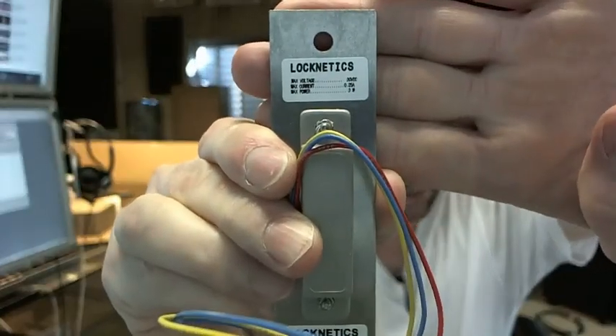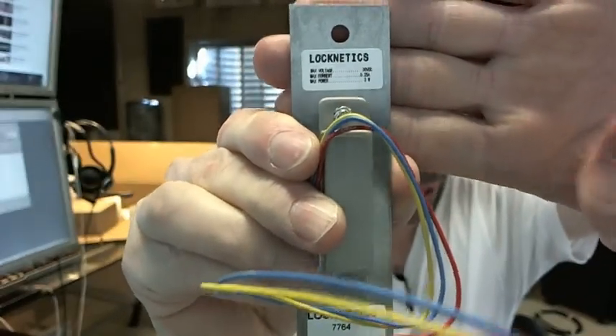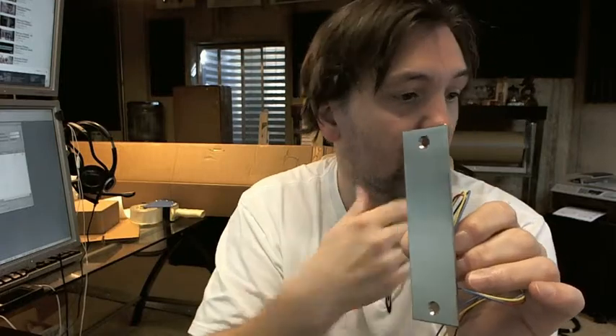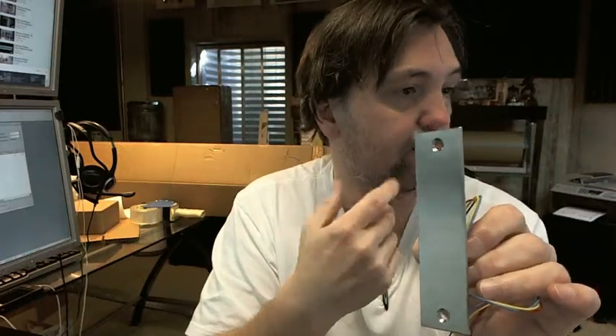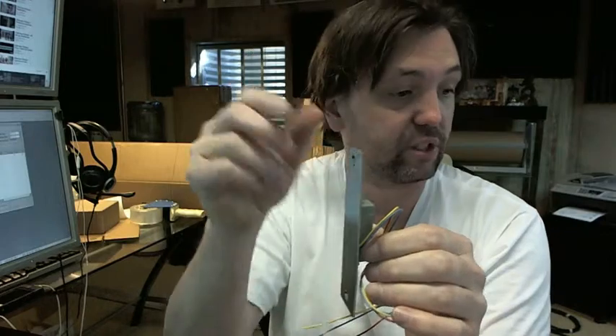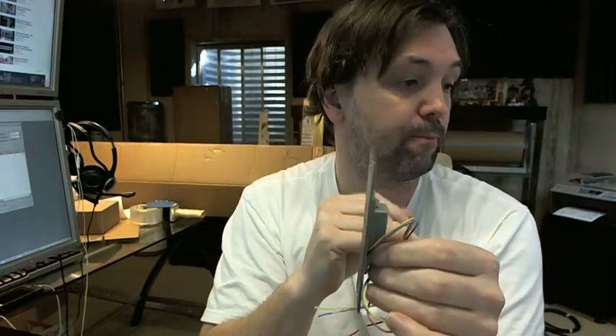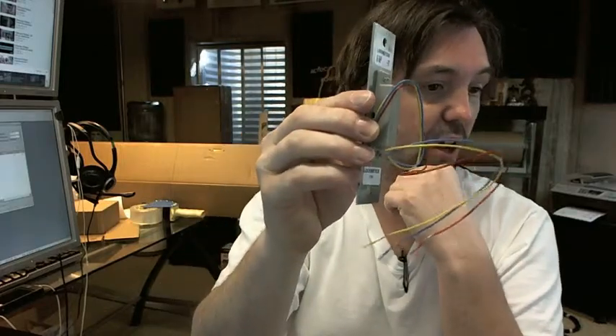Let's see if we can get the camera to focus on the label on the back of the magnet. The link to the template shows everything important dimensionally about the mortising in a wood door or a steel door — aluminum door for this — so I won't belabor all those dimensions here. The plate is quite thin, it's 5/64ths of an inch. 4 and 15/16ths, then you've got your body dimension as all indicated.